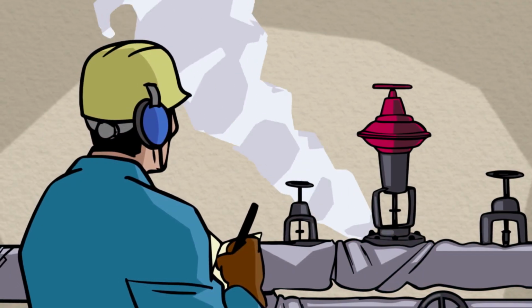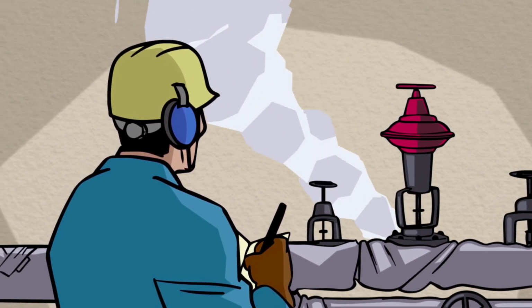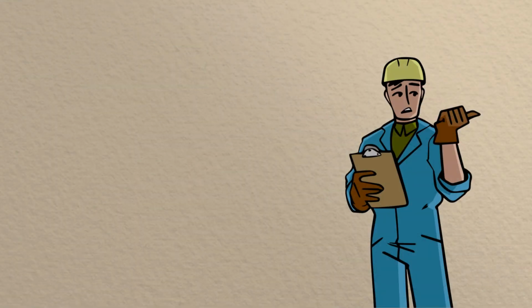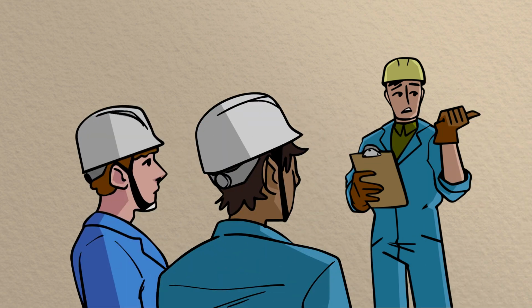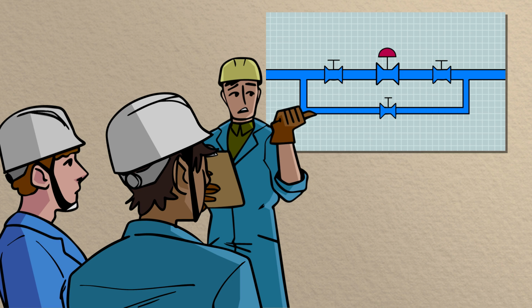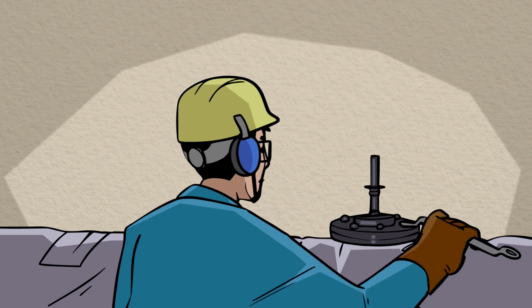When carrying out a routine inspection of the engine room, the first engineer noticed steam leaking from the main steam dump valve gasket. After the vessel arrived at the next port anchorage, he instructed the second and third engineers to stop the boiler operation and drain all steam and water from the system and ensure that it was completely empty and depressurized. Later, the first engineer was informed that the system had been drained and isolated, and he started to dismantle the valve to identify the cause of the leak.